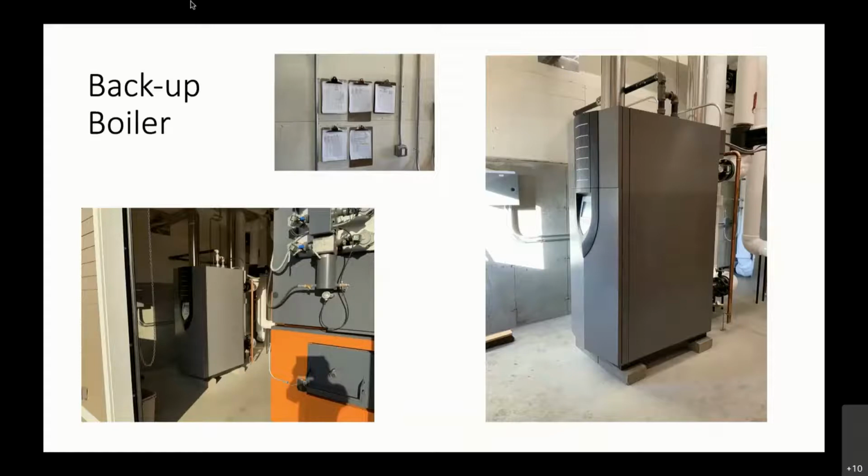When you see these kind of things, every day he does a physical check, checks around to see how the fire is running. He does a visual check, and once a week he rakes it out, and then he notates it down. And that's just so perfect. When I saw that, I thought that this boiler plant really will have a really nice life, because when you stay after a boiler like that, it will respond very well. It will not break down very often, but if you neglect any kind of machinery, of course sooner or later you'll be on the short end of that stick.